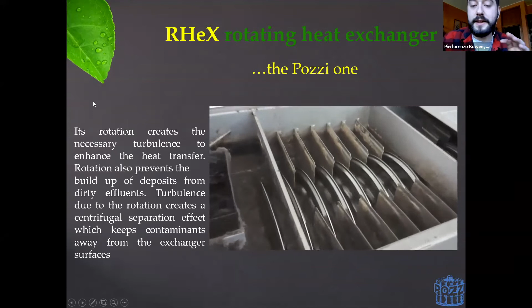To give you an estimation, with RHeX, our technology's constant efficiency is much better than any other type of technology, even a plate heat exchanger, which normally has a higher efficiency. But because you lose efficiency quickly due to fouling and clogging, and need to stop for maintenance, over time our solution is always much better.